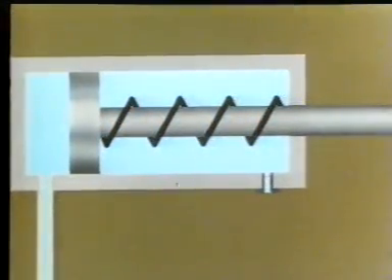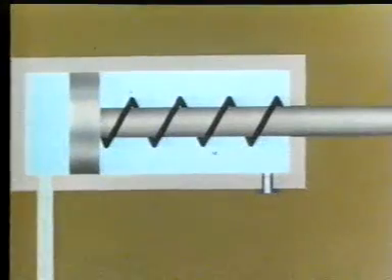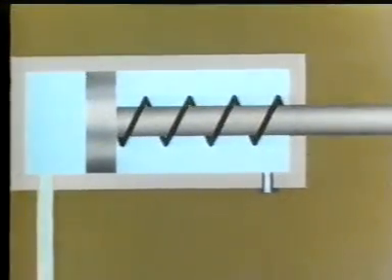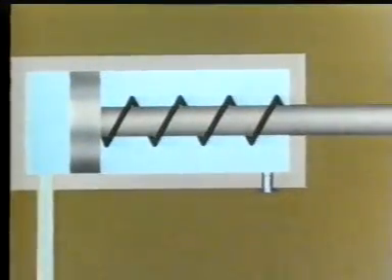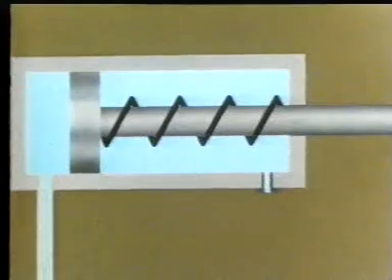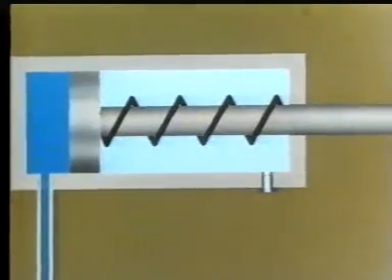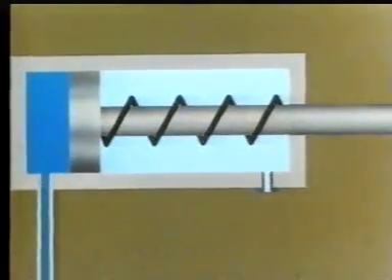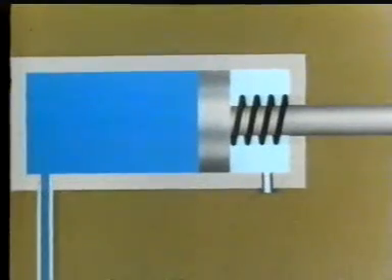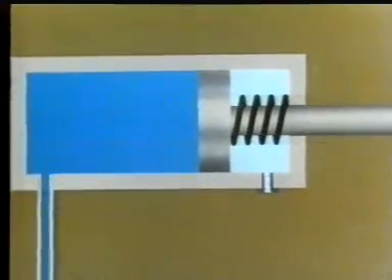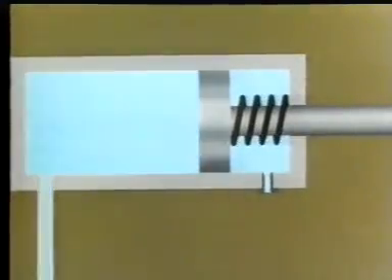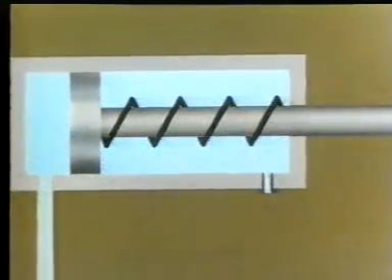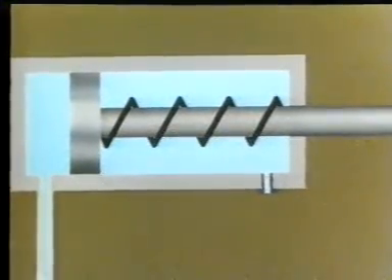This design of single acting cylinder can perform work only on the advanced stroke. If compressed air is applied to the piston surface, the piston rod moves out. If the cylinder space is exhausted, the reset spring forces the piston back to its initial position.